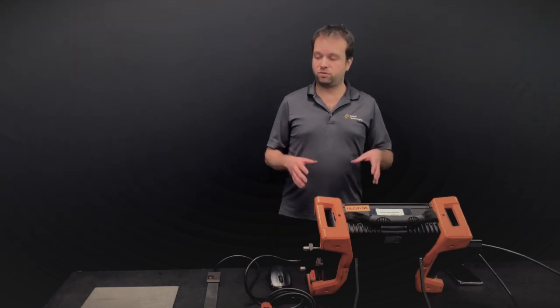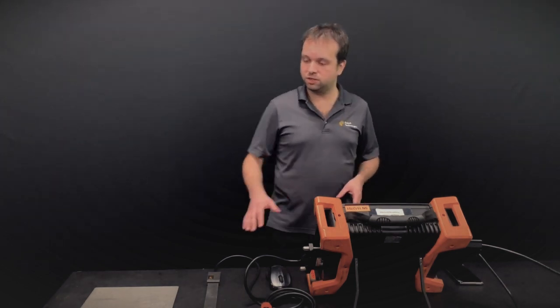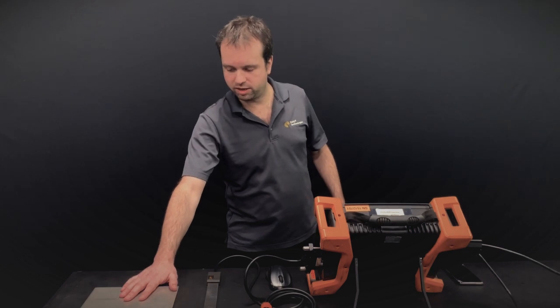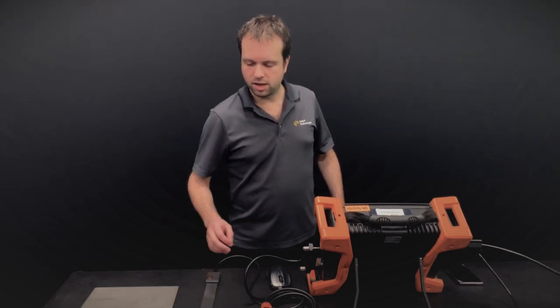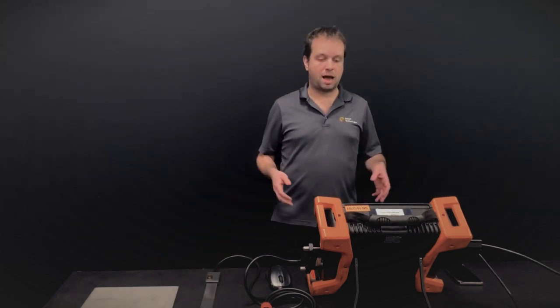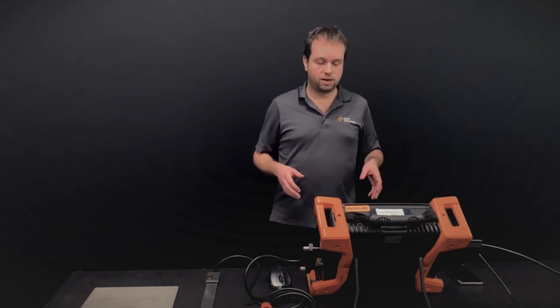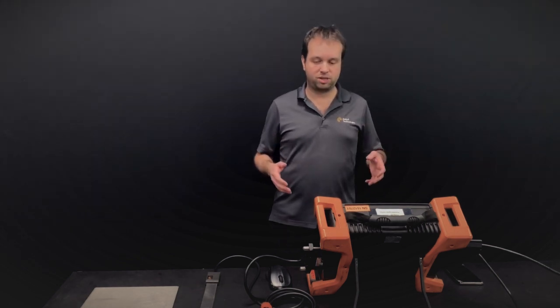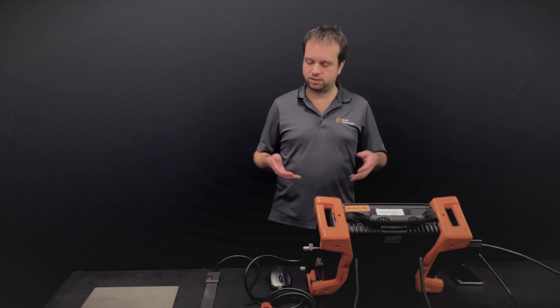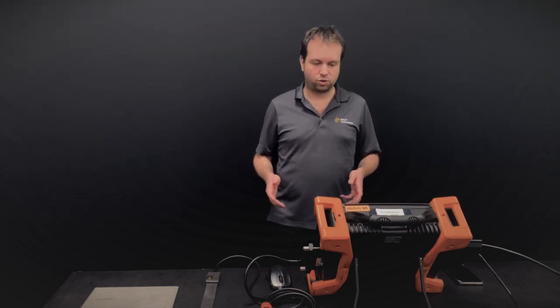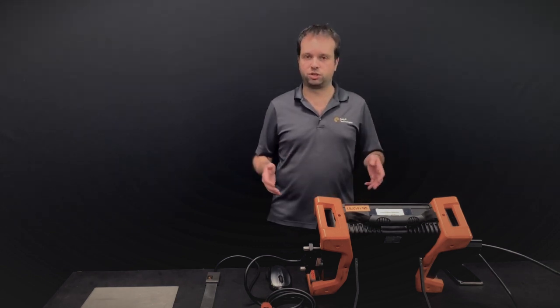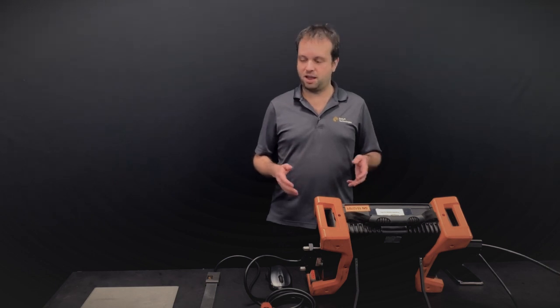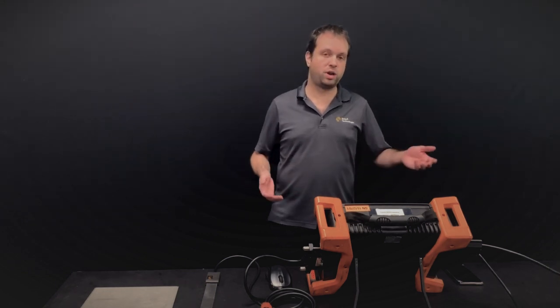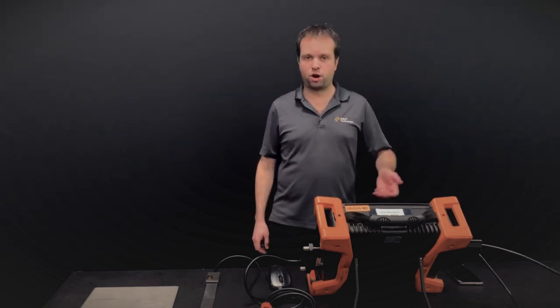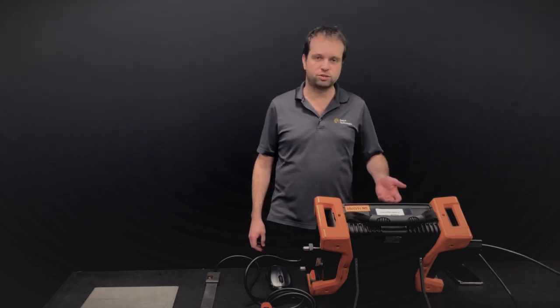So for the purpose of this video, I've just inspected this small stainless steel plate here with an iFlex probe. I'll use the mobile app and analyze the data on the Reddy, and the mobile app's going to allow me to add a lot of context to this small scan, so that I'll then produce an outcome, which is a small report, that anybody, even if they have no Eddy current array background, will be able to understand and appreciate and also trust.